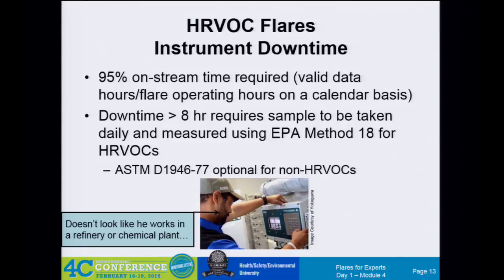We go to some facilities and ask, do you have a closed loop sampler? Some places say we have a ladder or platform we can get up on to attach a sample bomb or syringe and pull a sample. Others say they have tubing run down the grade, and then we ask, how do you handle the purge? Otherwise that tube is half or all full of oxygen, and when you take your sample, that whole tube volume ends up in your sample bomb, diluting the BTU content you want. You could be diluting unnecessarily by not having the correct samplers.